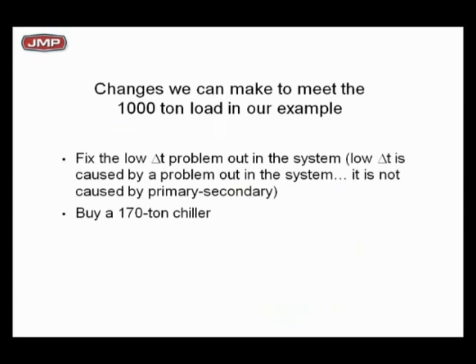But get this straight. It's not a primary secondary problem. It is a system problem. It's out in the system. So the easy thing is to get that 56 degree water up and fix your problem. If not, you're going to have to buy another chiller. That seems a little crazy to me, but we see this every day. Yeah, we see this delta T syndrome every day. We see people fixing it by buying a third chiller because they don't get the return chill water temperatures up.